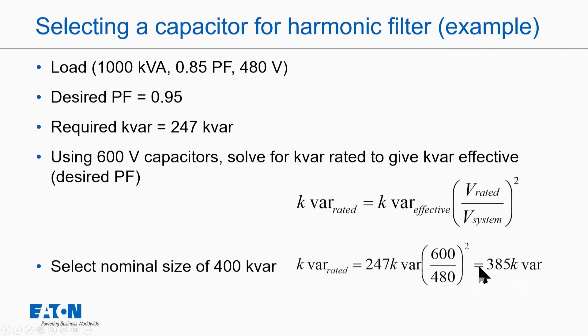divide by my applied voltage squared, I get 385. So in order to get the amount I need out of it, I'm going to go with a nominal 400 kvar capacitor.